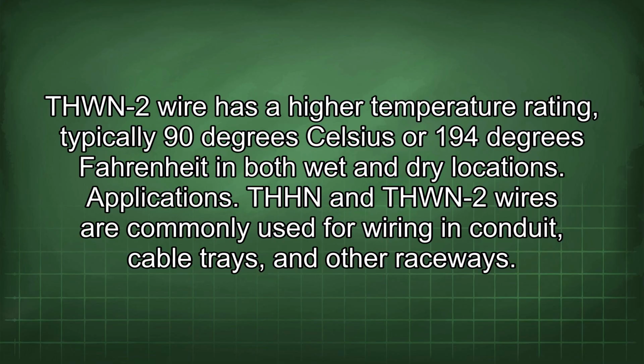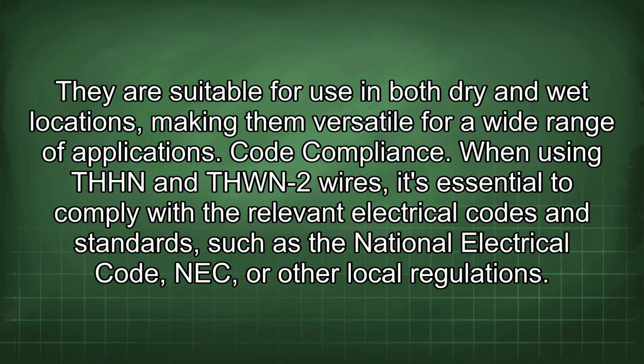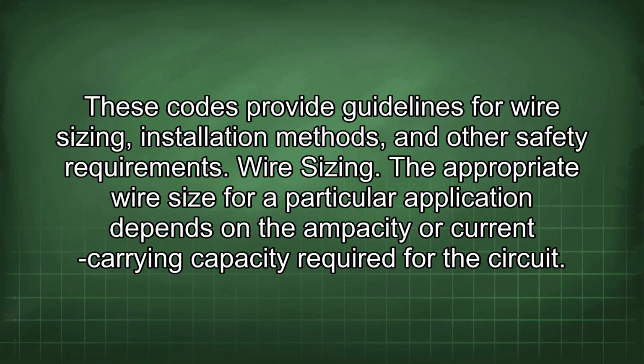Applications. THHN and THWN-2 wires are commonly used for wiring in conduit, cable trays, and other raceways. They are suitable for use in both dry and wet locations, making them versatile for a wide range of applications. Code compliance. When using THHN and THWN-2 wires, it's essential to comply with the relevant electrical codes and standards, such as the National Electrical Code, NEC, or other local regulations. These codes provide guidelines for wire sizing, installation methods, and other safety requirements.